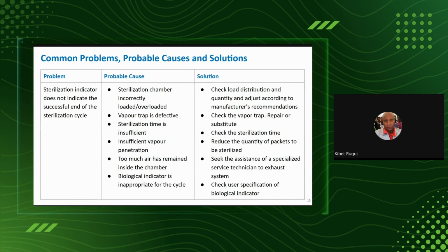The vapor does not penetrate to the equipment. So again, the sensors will not cheat you that there is enough penetration. And then there was not enough vacuuming, so there is still air in the chamber, and then the biological indicator is not the right one. So maybe you buy your biological indicators and you put them in there, and they are not the ones which were designed for that type of cycle. So it's good to know through the manufacturer which type of indicator you should use.